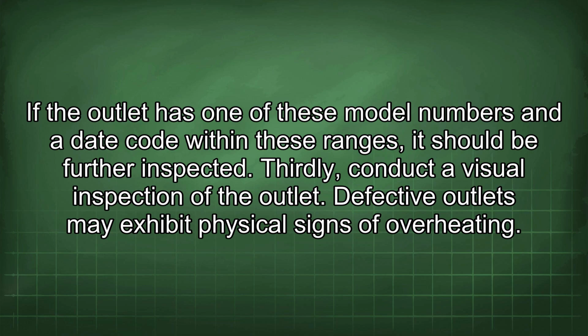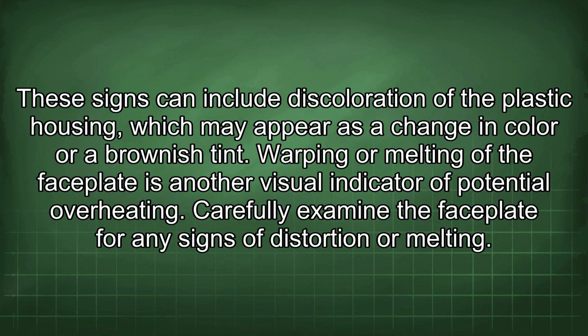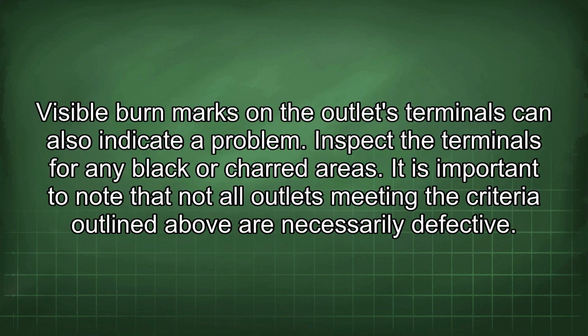Defective outlets may exhibit physical signs of overheating. These signs can include discoloration of the plastic housing, which may appear as a change in color or a brownish tint. Warping or melting of the faceplate is another visual indicator of potential overheating. Carefully examine the faceplate for any signs of distortion or melting. Visible burn marks on the outlet's terminals can also indicate a problem. Inspect the terminals for any black or charred areas.